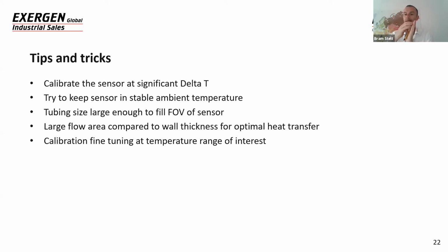An IR sensor will measure anything that's in the field of view. It will give an average temperature of all the objects in the field of view. Now, if you want to measure a tube, make sure that the tube completely fills the field of view of the sensor, because if not, if you have a very small tube and the sensor looks, let's say, around it, then that will also affect the measurement. It will be part of your temperature measurement.